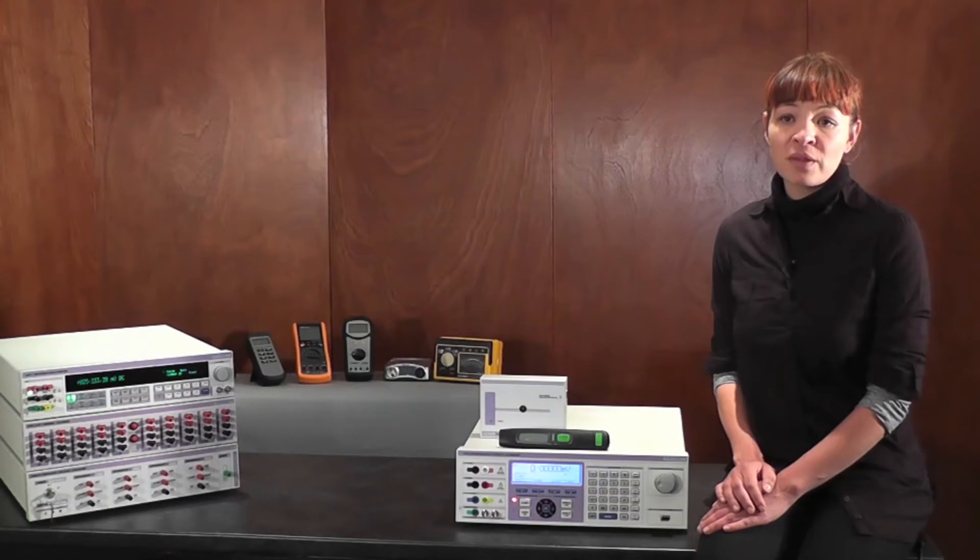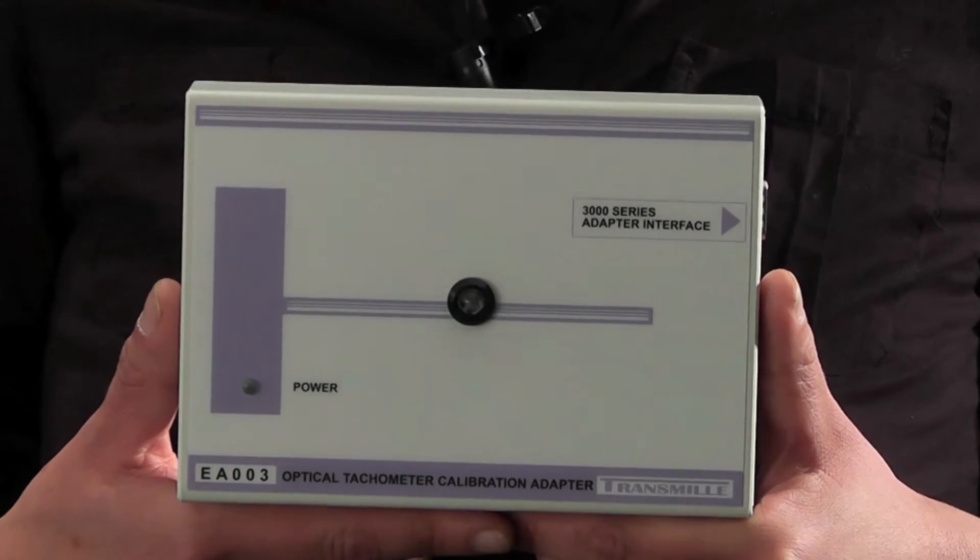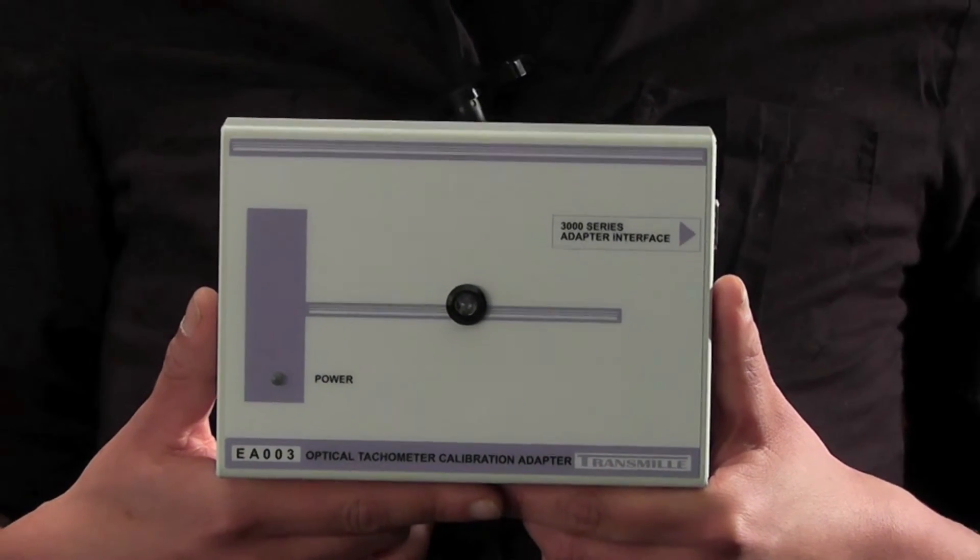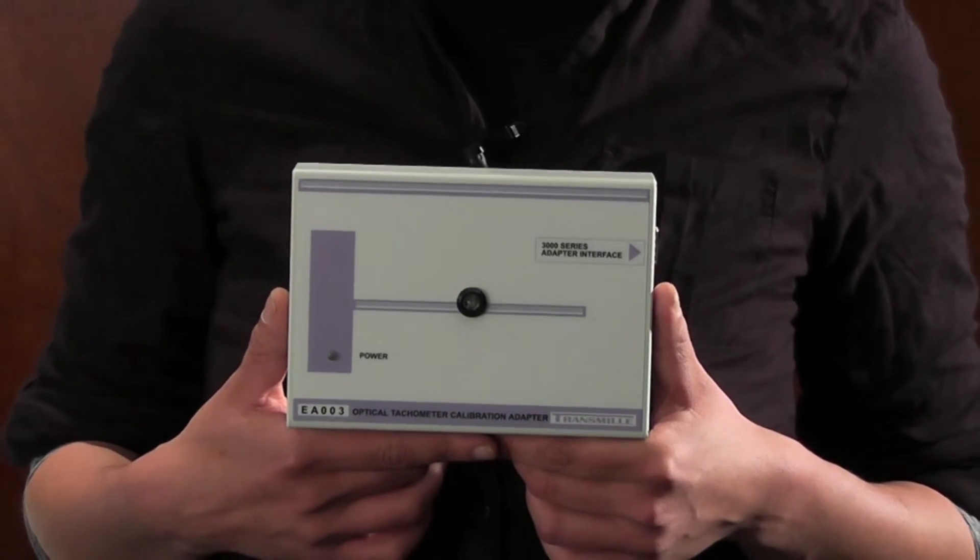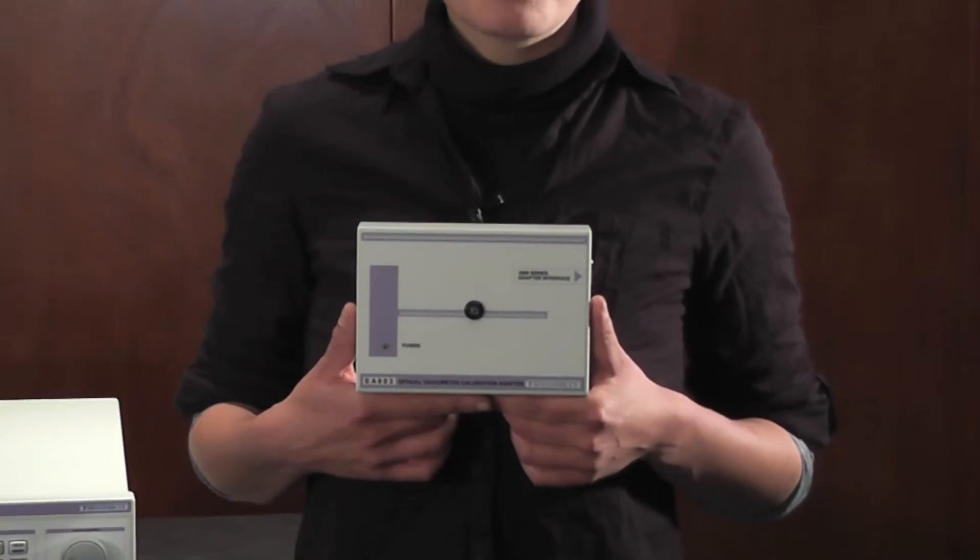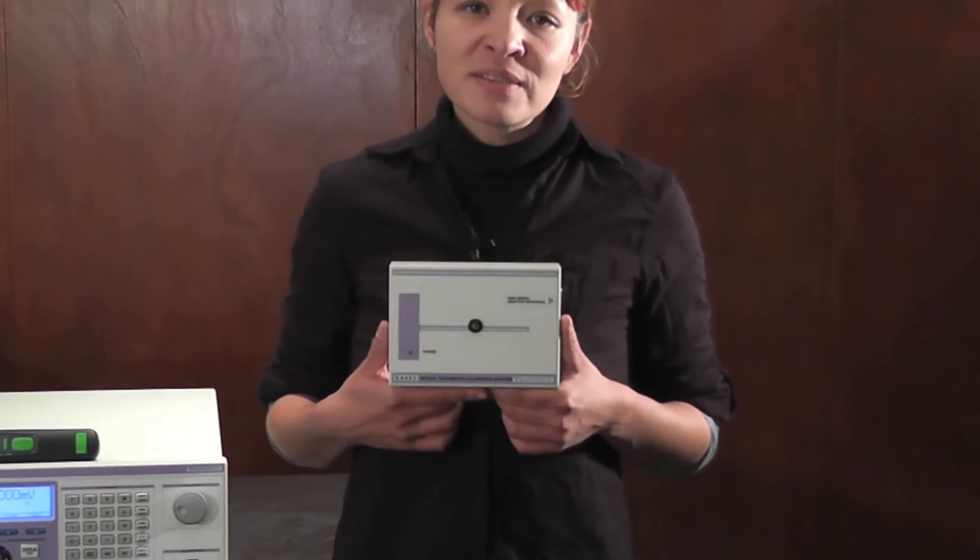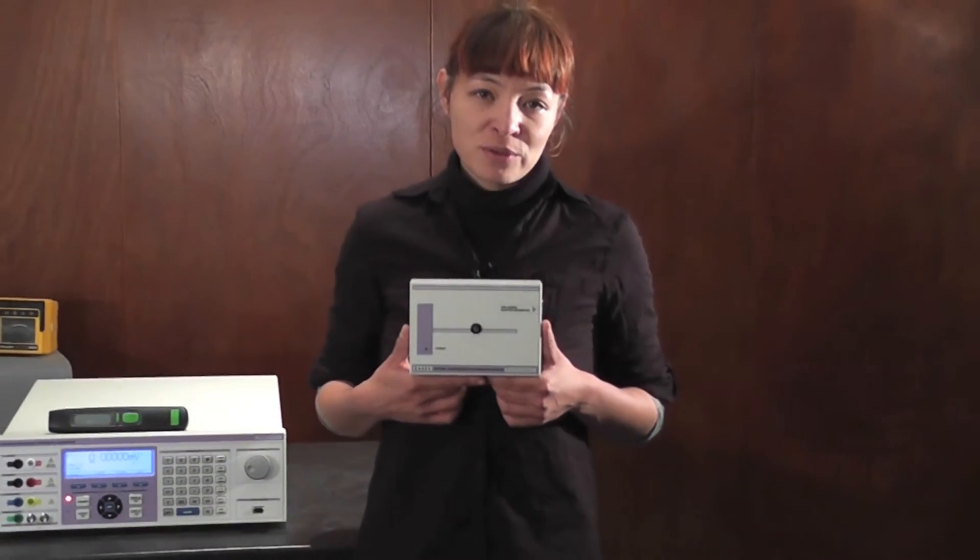Quality control systems in place within industrial work environments typically require the calibration and certification of these devices. The optical tachometer calibration adapter EA003 is an external adapter that has been designed to be used with the 3000 series calibrator to calibrate optical tachometers with a range of 60 to 60,000 revolutions per minute.